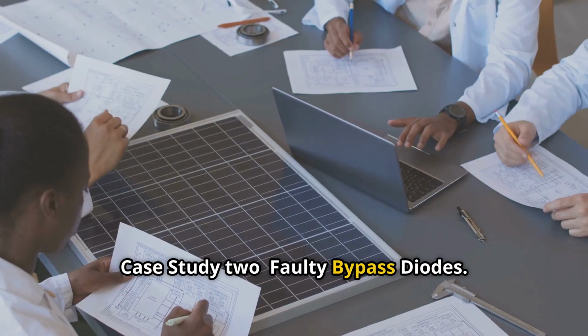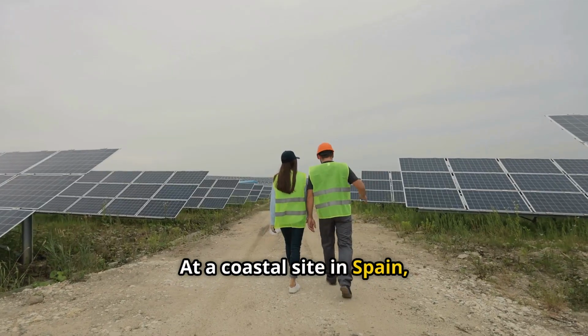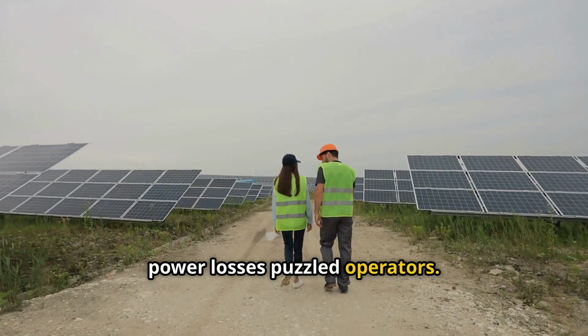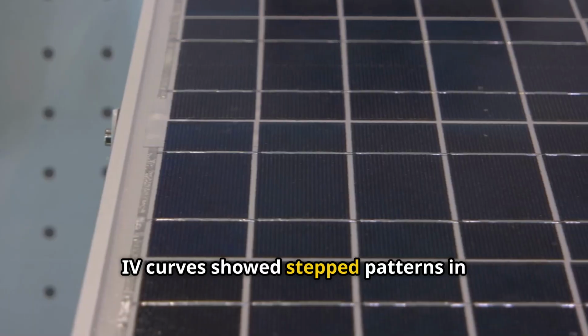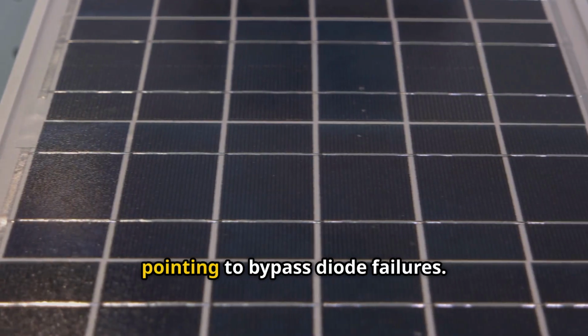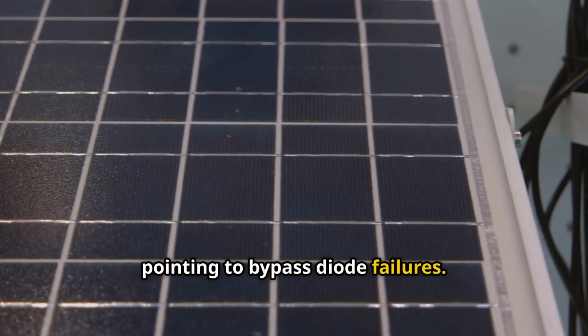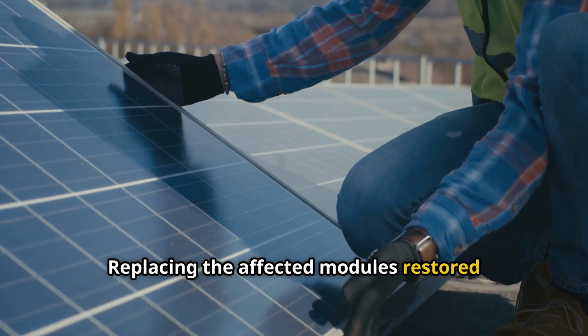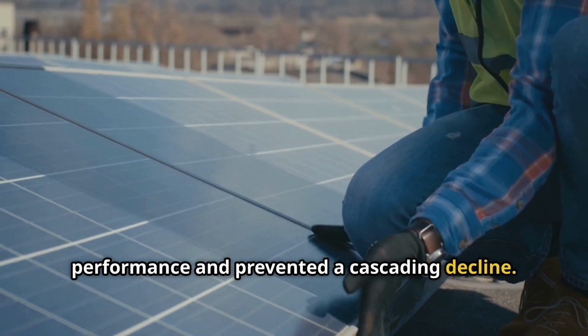Case study 2: faulty bypass diodes at a coastal site in Spain. Power losses puzzled operators. IV curves showed stepped patterns in specific strings, pointing to bypass diode failures. Replacing the affected modules restored performance and prevented a cascading decline.